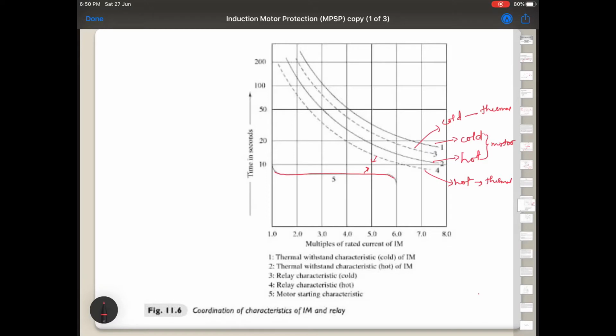While selecting the thermal relay for thermal overload protection of an induction motor, it must be assured that the relay shall not operate when the motor is starting. So when the motor is starting, this relay should not operate. Hence, as I said, the curves should not overlap. If they overlap, the relay will operate during the starting condition itself, and your motor may not start up. That happens when your motor is initially running with a heavy load, or when the load inertia is too high. If you are running a motor with a high inertia load, then this problem may occur.